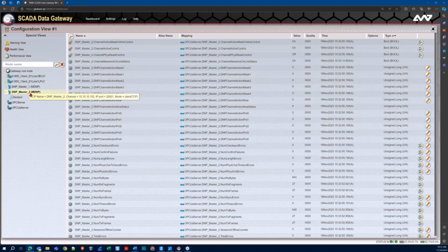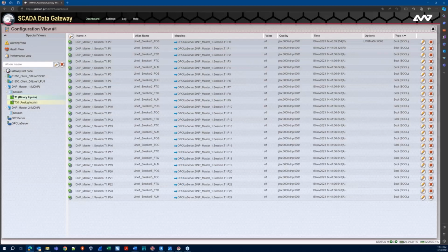But in other cases, I might not actually have that DNP3 outstation available on the network while configuring the gateway. This is pretty common — you might be configuring the gateway at your desk before getting out into the field and having it installed with all devices available. So we do have some options as well. I could basically create the points manually.